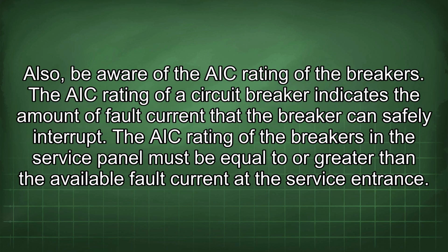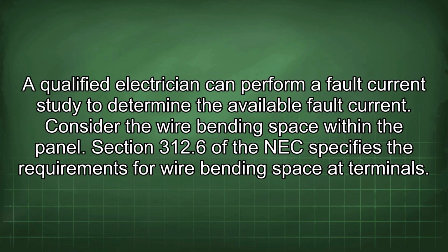Also, be aware of the AIC rating of the breakers. The AIC rating of a circuit breaker indicates the amount of fault current that the breaker can safely interrupt. The AIC rating of the breakers in the service panel must be equal to or greater than the available fault current at the service entrance. A qualified electrician can perform a fault current study to determine the available fault current.